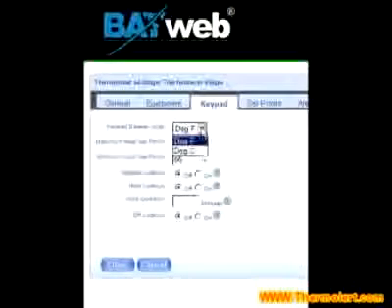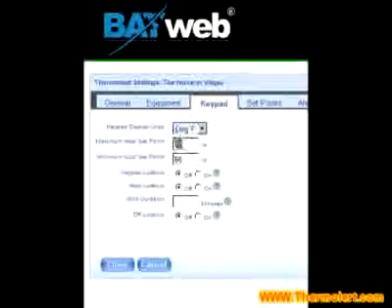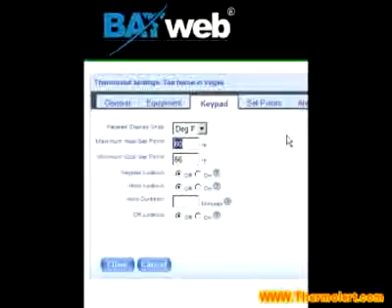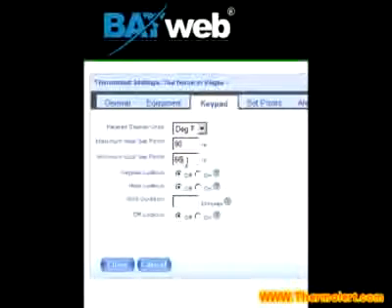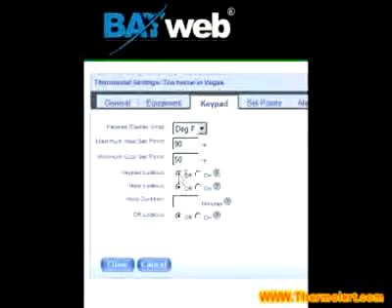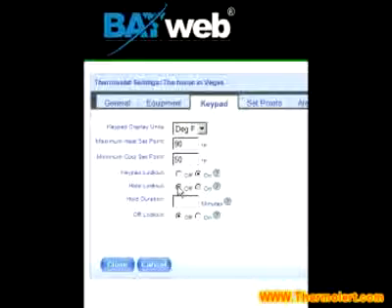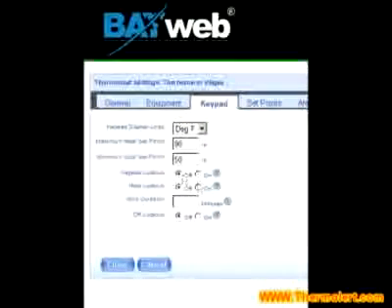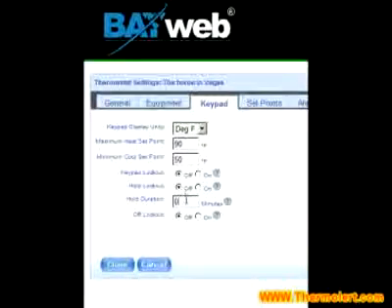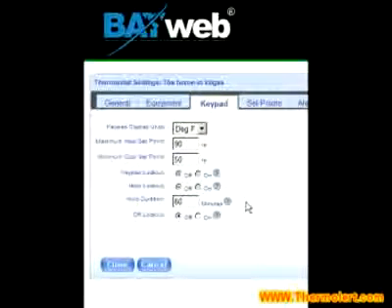The next tab is the Keypad tab, and you can select various options on the keypad. You can select the temperature display in Fahrenheit or Celsius. You can also limit the keypad to allow people to go up to 90 degrees or not below 50 degrees. You can lock out the keypad entirely, and you can lock out the hold button so people can't override the software's control.